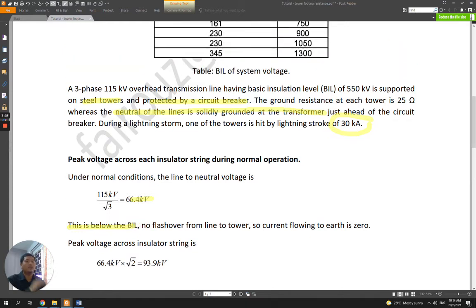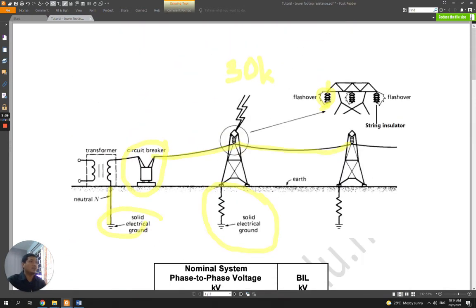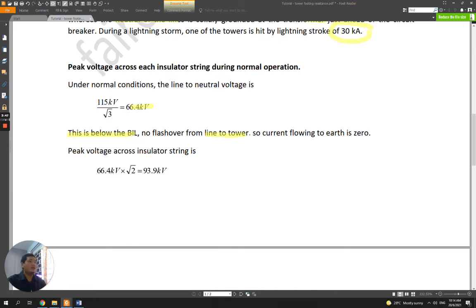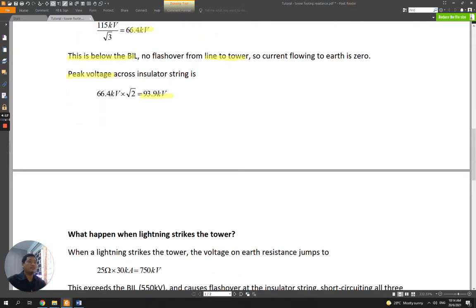BIL is 550 kilovolt. So because the voltage is below BIL, there's no flashover from line to tower. There's no flashover from line to tower because the voltage is very low, below the BIL. So current flowing to earth is zero. And then even at peak voltage, 66.4 kV times square root of 2, 93.9 kV, this is also below the BIL value. So during normal operation, there's no flashover to the line.